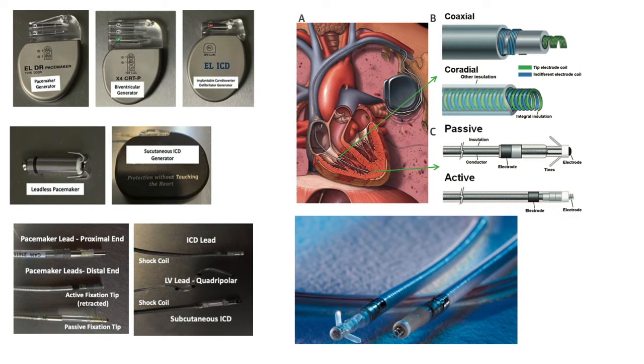The pacemaker or the pulse generator has a power source. This power source is mainly lithium iodine cells, and it is connected to the microcircuit. This microcircuit controls the characteristics, functions, and timings of the generated impulse. This whole unit is encased in a tight-sealed titanium can, and this power source provides a lifespan of about 5 to 15 years depending on the complexity of the system, the programmed output, which features of the pacemaker are programmed on, and how much the generator is being used by the patient.